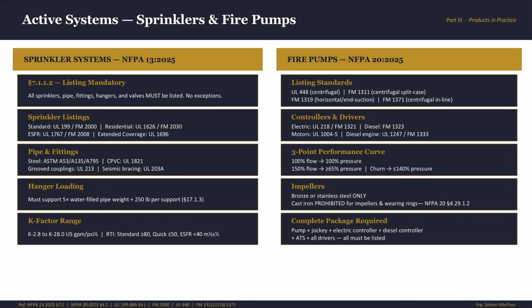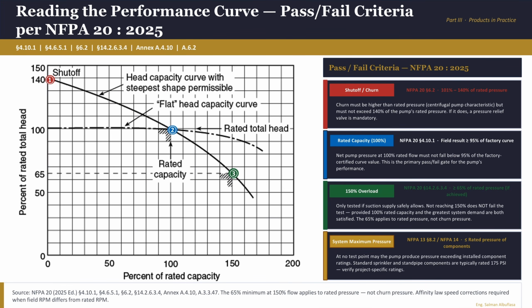And now, how do we verify it? From this, reading the performance curve, the pass-fail criteria per NFPA 20. It might look too complicated. A lot of people do not understand this curve, but let's simplify it. We have the x-axis and the y-axis. The horizontal axis is how much water is flowing, 0 here and 200 here. It's percent of rated capacity. And the y-axis, or the vertical axis, is how much pressure the pump is producing. 0 at the bottom, max at the top. That's it. So this is pressure and this is the water flow.